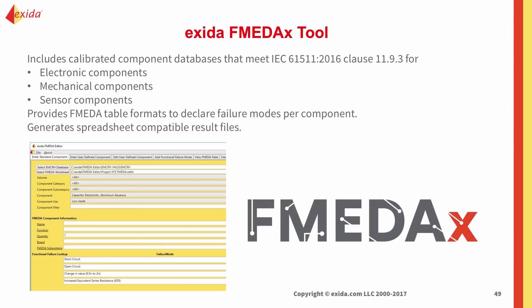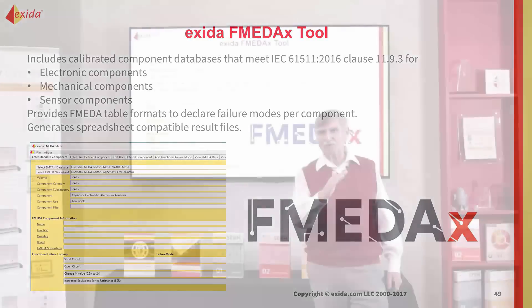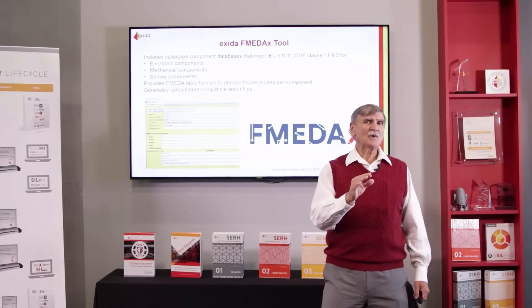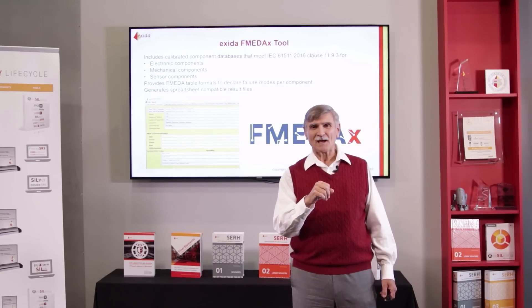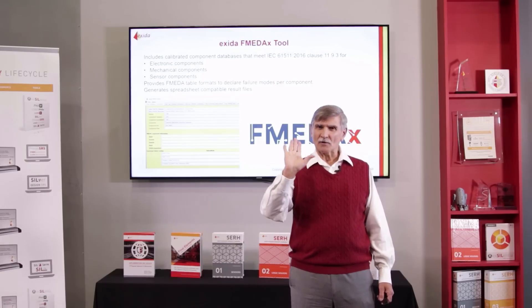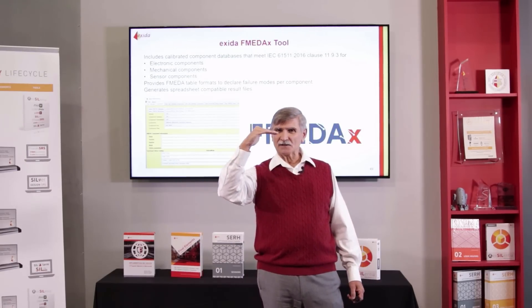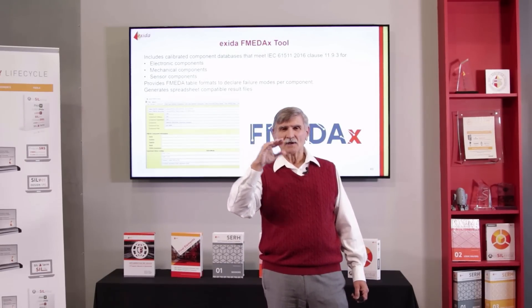exida does have an FMEDA tool called FMEDA X. It now has a calibrated electronic, mechanical, and sensor database that is generating really accurate — relatively accurate — predictions. Do we know this is exactly right? No. Obviously we'd like more data and we're working on that. But for the time being, if we're a little bit conservative by generating slightly higher failure rate numbers, that's okay.